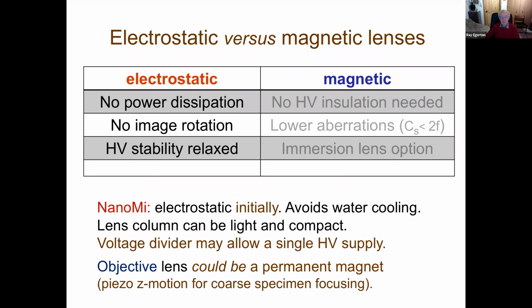So because we've relaxed the requirement on resolution, we can take another look at this question of electrostatic or magnetic lenses. And in fact, our decision was to look into electrostatic lenses. There are some advantages in terms of electrostatic lenses. They consume no power, which means that the lenses do not need water cooling. That's an advantage if you want to put a lens column inside a vacuum system that may have other components associated with it.